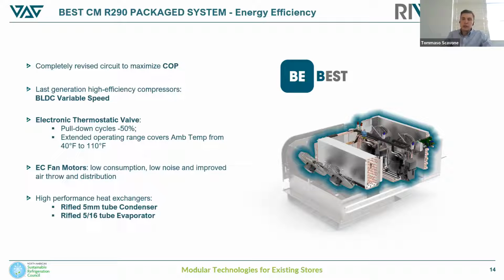Regarding the coils, thanks to sophisticated simulation software and extensive tests, we're able to define the best geometry and piping circuit to maximize the performance of the condenser, where we are adopting a 5mm rifled tube and a 5/16 rifled tube on the evaporator. So very small tubes, but with increased transfer surface thanks to the rifle technology. Less volume, reduced charge, and increased heat exchange, therefore better product efficiency in general.